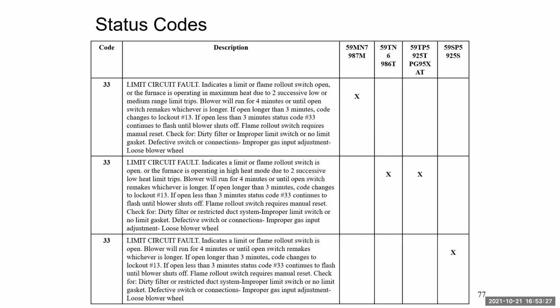Now, 33, limit circuit fault. I bring this up because if none of you have experienced it yet, you're probably going to. On the new 4.05 software that just came out for our UIs, and I think it was in 3.94 also, but it was really pushed in on the 4.05. You will get to a call, and on your UI or your customer will call you and tell you, I have a fault 126. It's 126 fault code on my thermostat and it's saying a high heat cycle active. This is Carrier's way of not freaking a homeowner out that they have a limit trip going on. 126 means 33 on the furnace. Again, 126 on the UI, 33 on the furnace. Your furnace has been into limit trips. You have to have 2 consecutive limit trips for it to register the 126 on the thermostat.